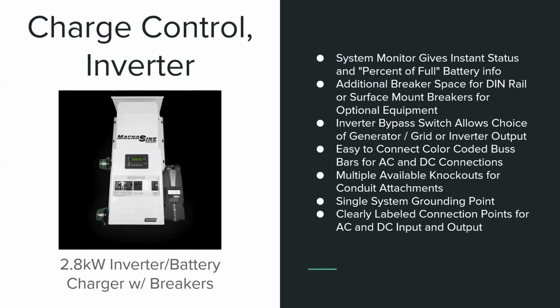That way you can quickly see how full your batteries are. There are additional breaker spaces in there if you want to add more. The inverter bypass switch allows your choice of generator or grid or inverter output. If you want only generator output going, it's very flexible. It's easy to connect, with color-coded bus on the inside, and for AC and DC connections it has multiple available knockouts for conduit. It has a single system grounding point, and clearly labeled connection points for AC and DC input and output to make connections to your generators and your AC output, whether that be on an SO cord or just a standard receptacle.